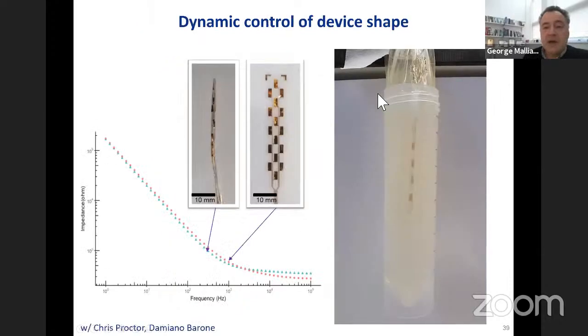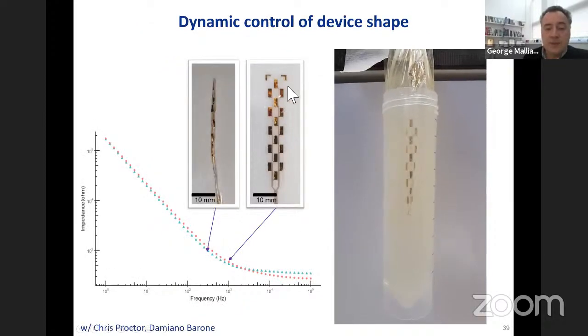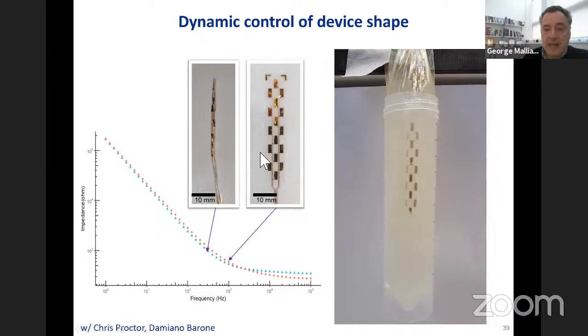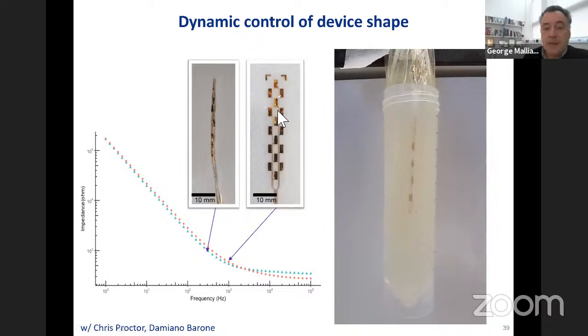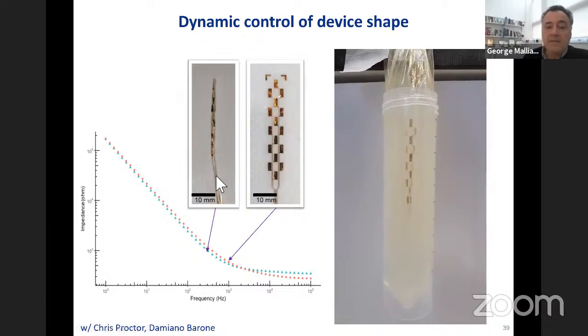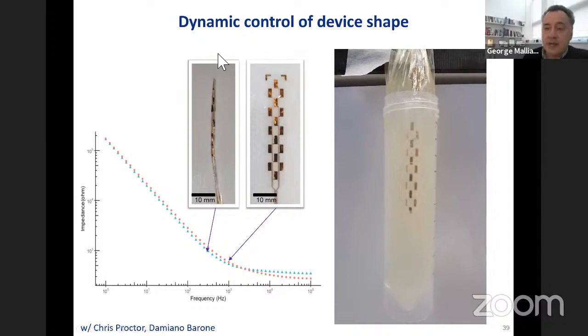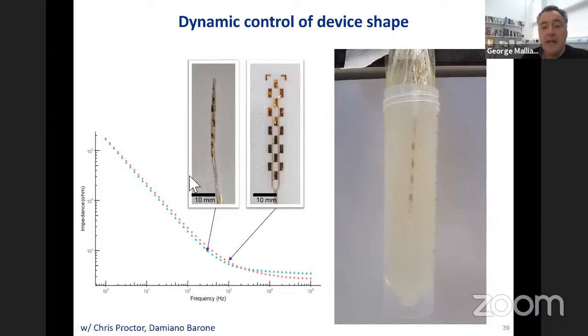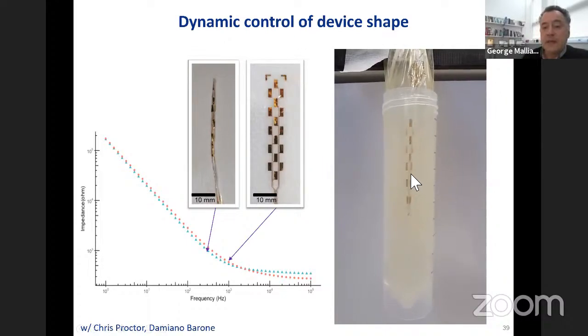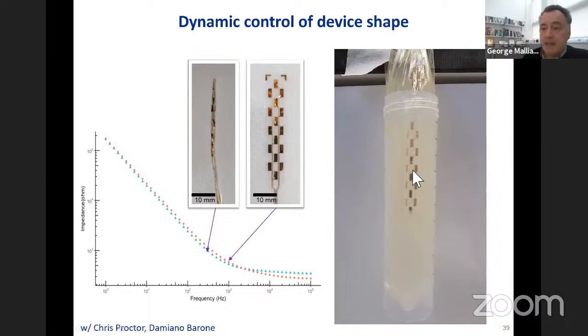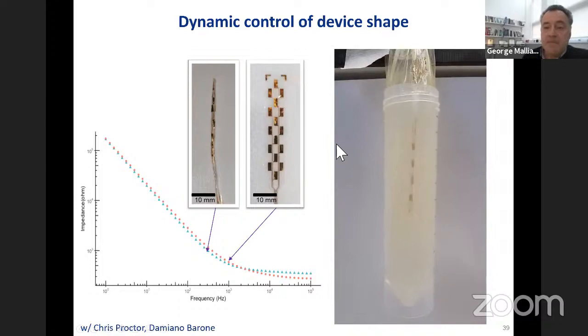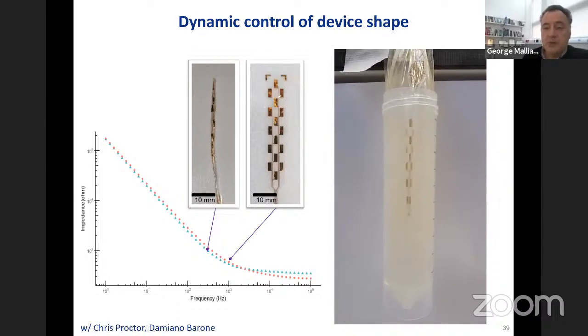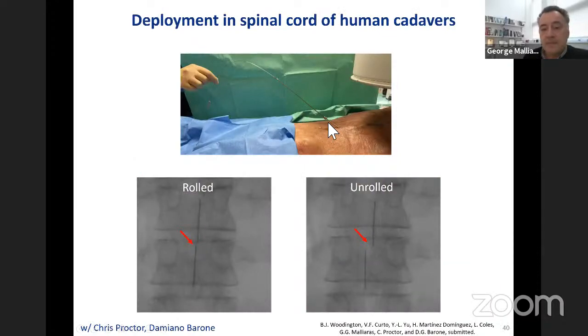These devices now allow you to make paddle-like electrodes that would normally require a laminectomy to be placed. But these electrodes can be rolled up to have the same shape as a percutaneous electrode that can be implanted in the body using a spinal tap. Then, through pneumatic actuation, it will open up and become a paddle. So you decrease quite dramatically the impact of neural surgery. You can place those with a spinal tap, as shown here.